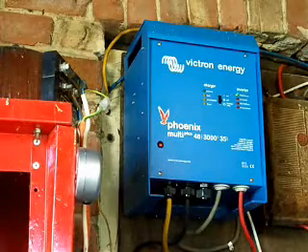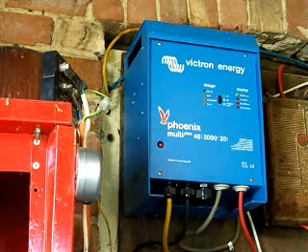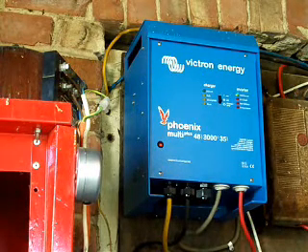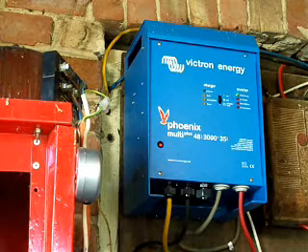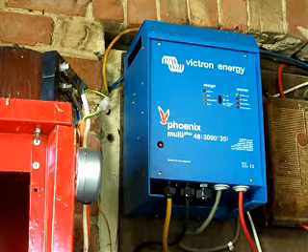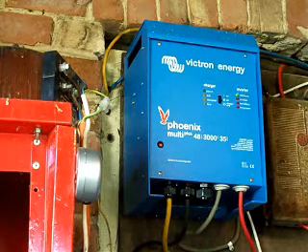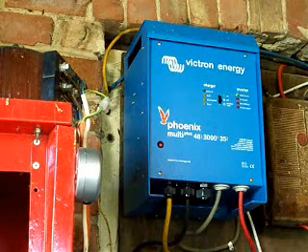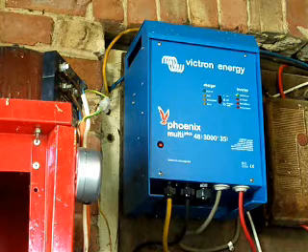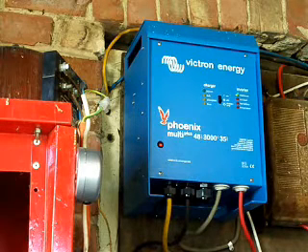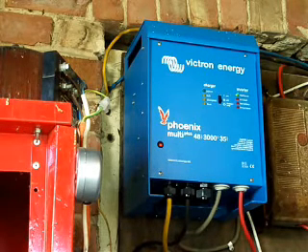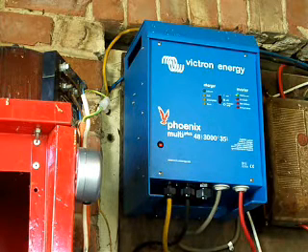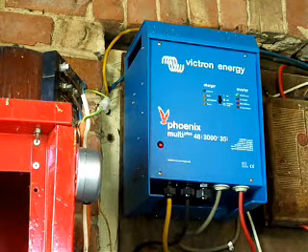This is the inverter. It takes the battery power at 48 volts in this case and changes it into mains power at a true sine wave. In this case, this inverter is also a UPS inverter, in so much as when the batteries get low, then it will automatically change over to mains power. The parameters for this function are fully adjustable.